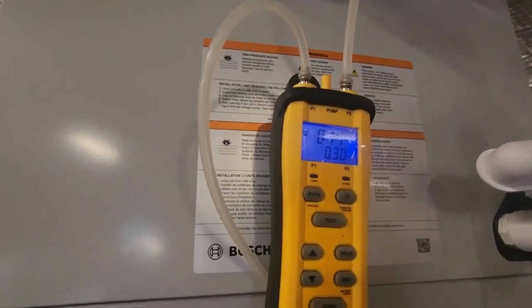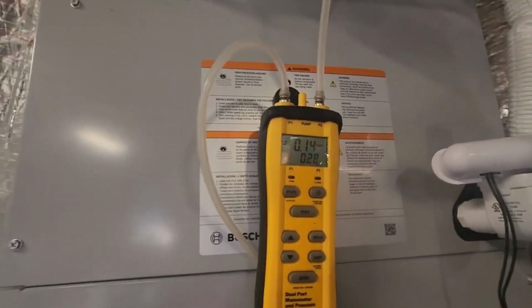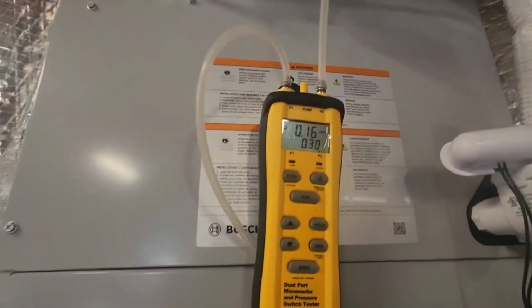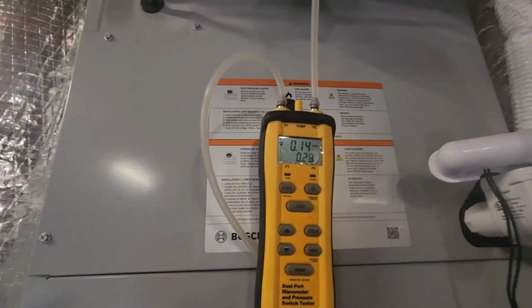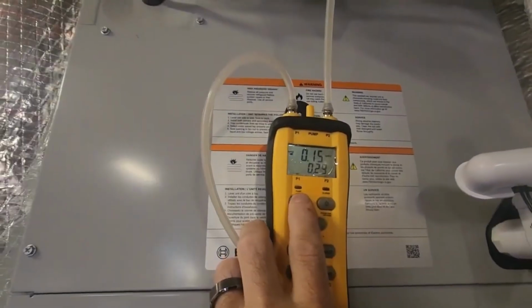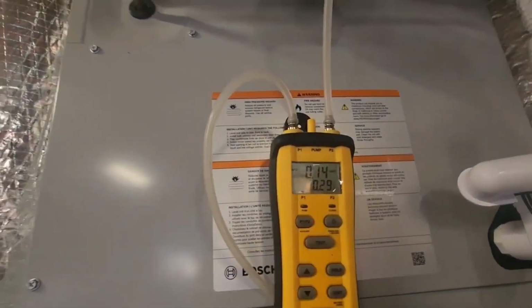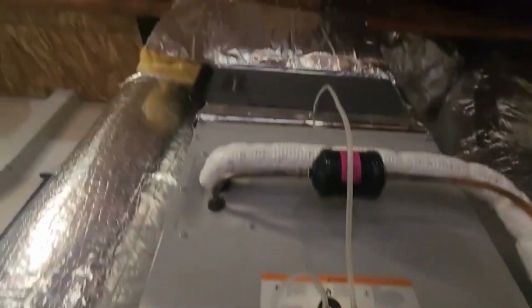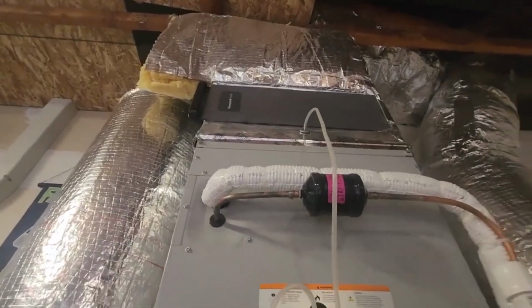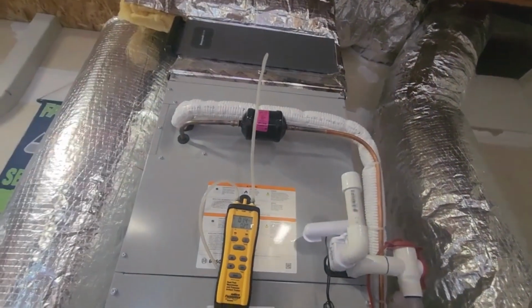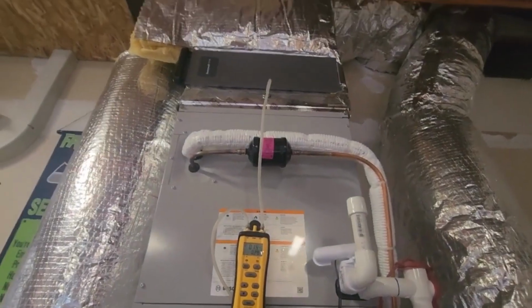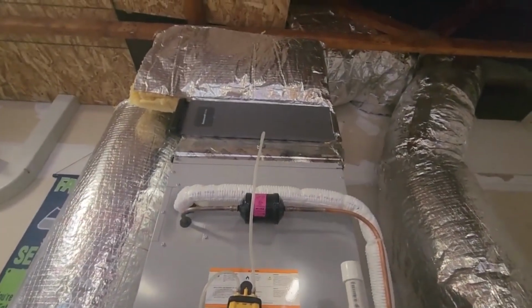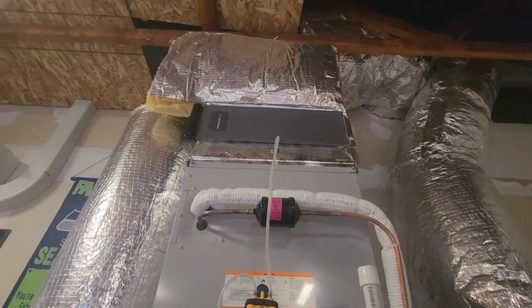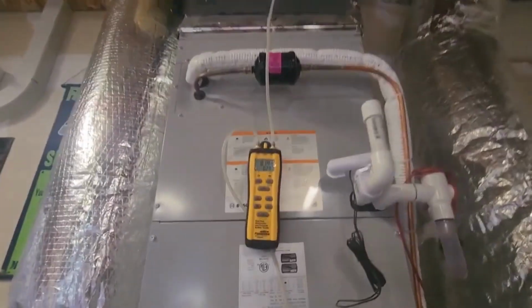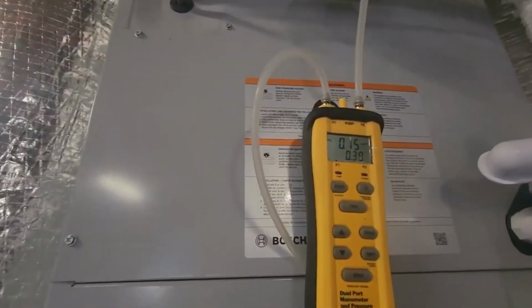Look at that. Still 0.14 in our supply, and look what it being on first stage does for us on our return. So our return's only at 0.14 now. So those filters are awesome. That's my entire return run with my filters, 0.14. That's awesome. That's why it's so important to keep your filters clean, guys. It'll keep your equipment running a lot longer, and it'll keep it running more efficiently for sure.